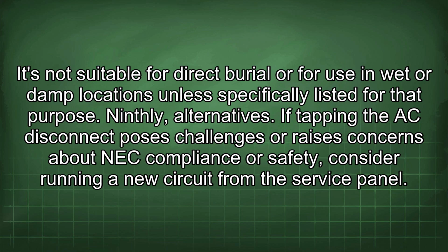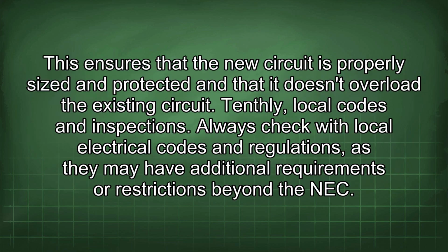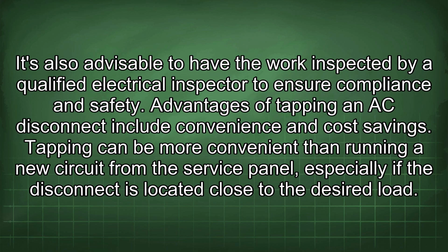Ninthly, alternatives. If tapping the AC disconnect poses challenges or raises concerns about NEC compliance or safety, consider running a new circuit from the service panel. This ensures that the new circuit is properly sized and protected and that it doesn't overload the existing circuit. Tenthly, local codes and inspections. Always check with local electrical codes and regulations, as they may have additional requirements or restrictions beyond the NEC. It's also advisable to have the work inspected by a qualified electrical inspector to ensure compliance and safety.